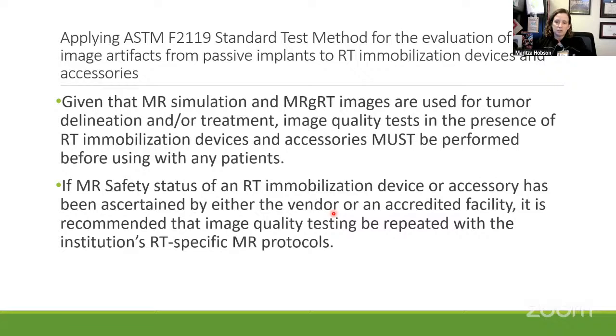So if the MR safety status of an RT immobilization device or accessory has already been ascertained by the vendor, an accredited facility, or in-house, it is recommended that the image quality testing be repeated with the institution's RT-specific MR protocols, and the RF coils to be used with the RT immobilization device, with proper coil filling with a phantom and similar setups as used in clinical use. That allows us to properly ascertain any potential imaging artifacts, including field of view limitations, which may lead to aliasing artifacts. So we're using it as we would clinically, right, with our clinical protocols.